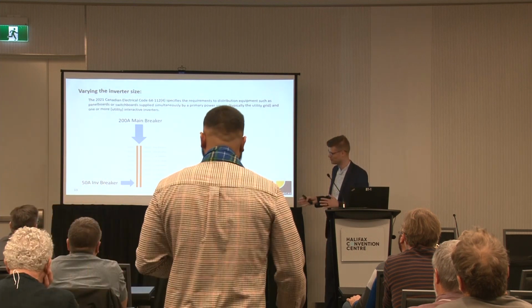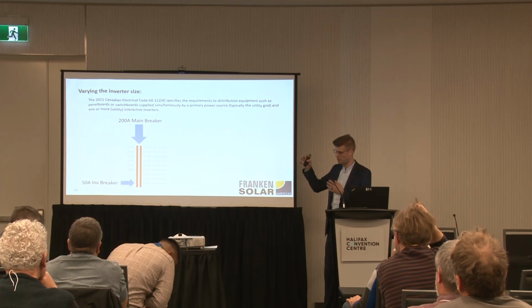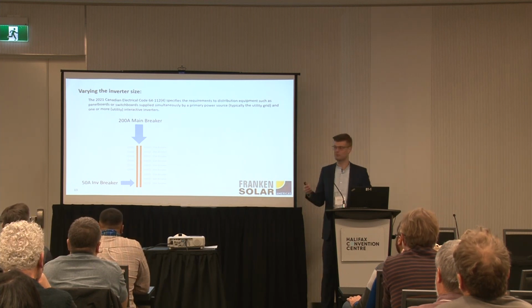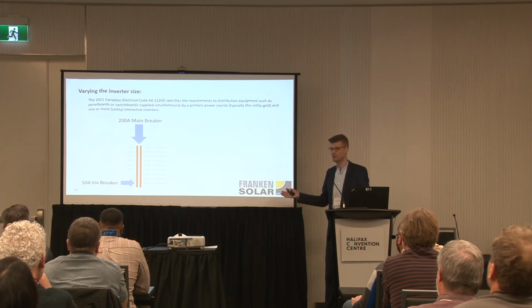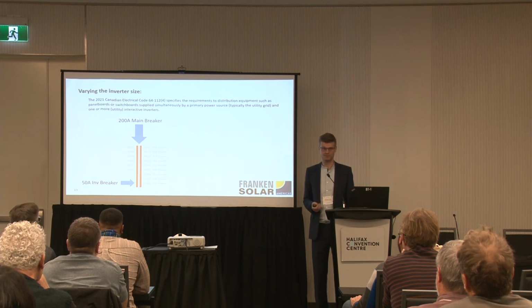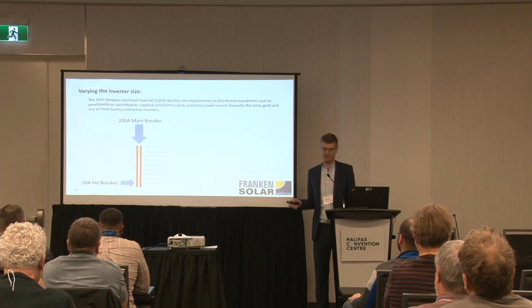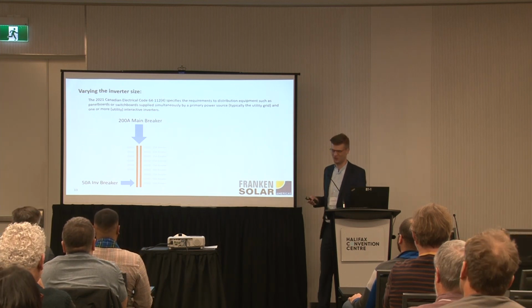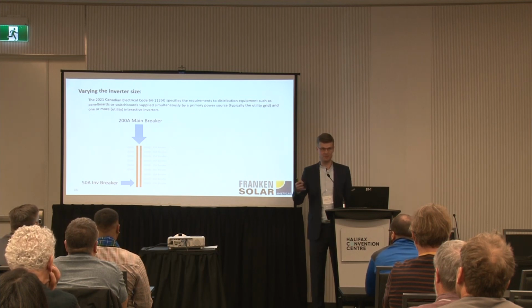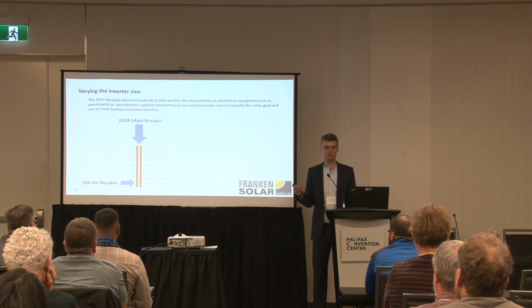And here we come directly to a different topic, which is directly related. When we vary the inverter size, we typically, from an installation perspective, are looking at what the infrastructure of the customer can actually take. Most customers have either a 100 amp service or maybe a 200 amp service, and depending on their system, they may or may not have to change the electrical panel. An electrical panel change is a big deal for a customer who just wants to have solar because he didn't know he needs a new electrical panel in the first place when he thought about reaching out to an installer to get solar. So giving this guy a new electrical panel at a couple of grand or even more, depending on what your electrician is charging you, doesn't add any value to the customer's solar system. It just makes the solar system more expensive.